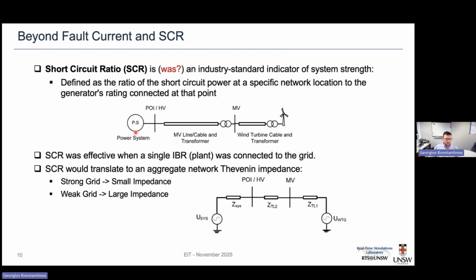So you can see we translate this whole power system into an equivalent network here: high voltage, medium voltage, transmission lines, system impedance up to the point of connection. A small impedance from this point of connection back to the equivalent network would generally guide us towards a strong grid, and a relatively large impedance would give us, of course, less control of the voltage waveform, a lot more local impact on the voltage waveform at the point of connection of any new generator, and that would hint towards a weaker grid.